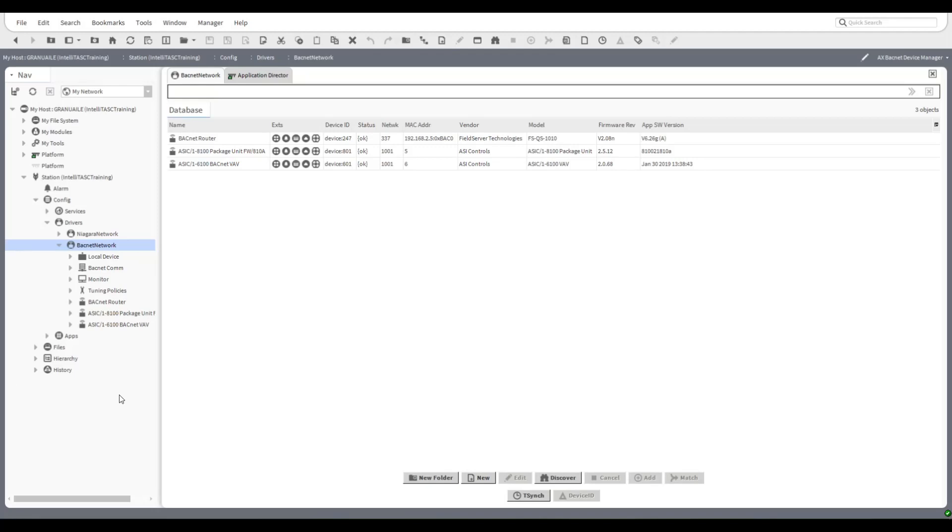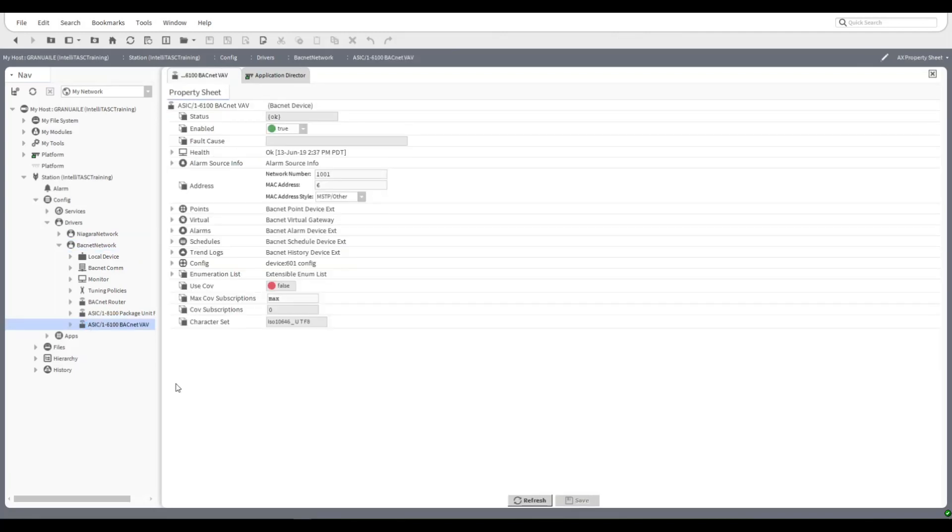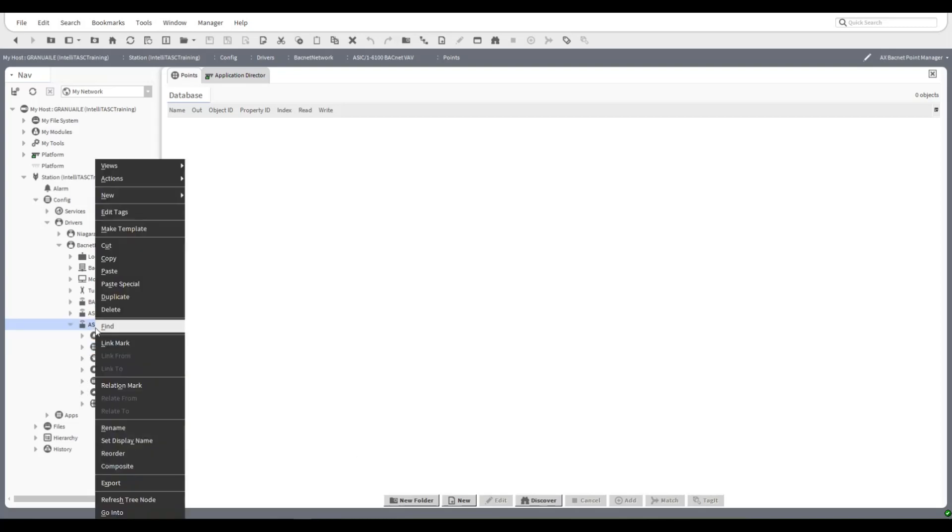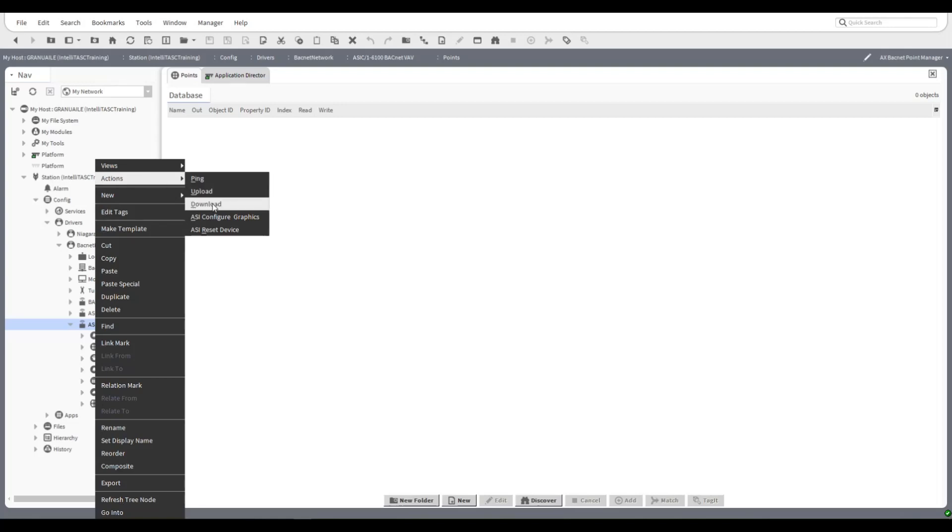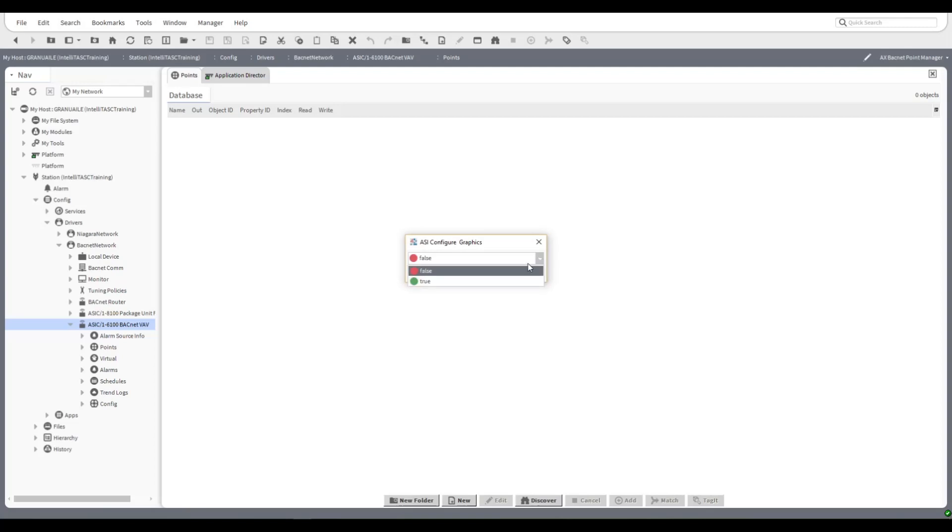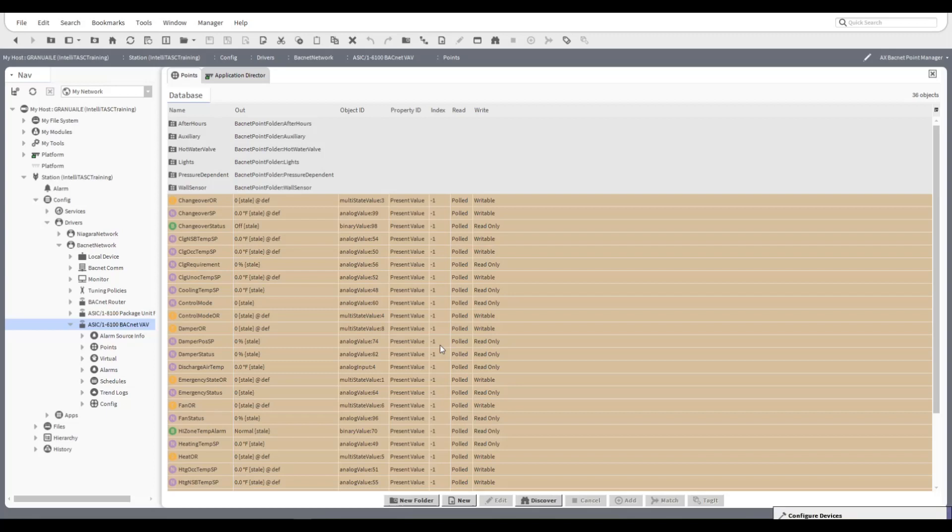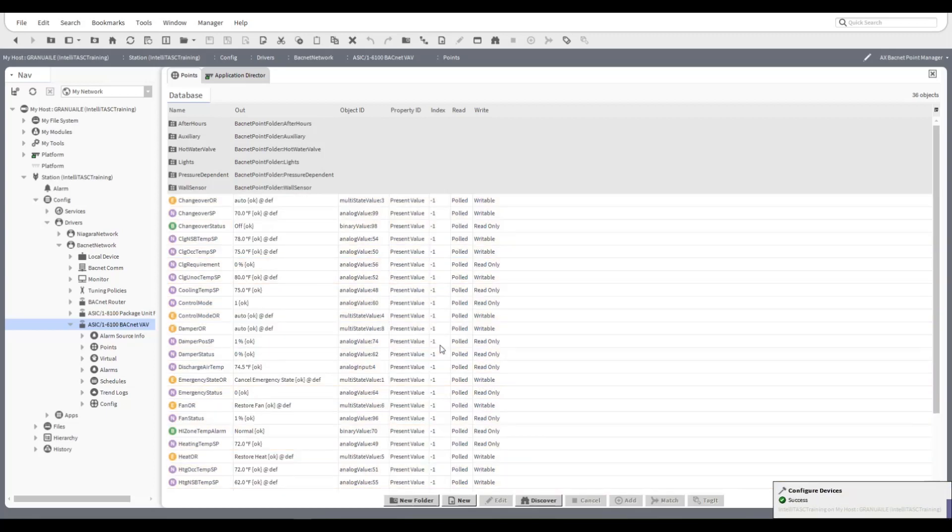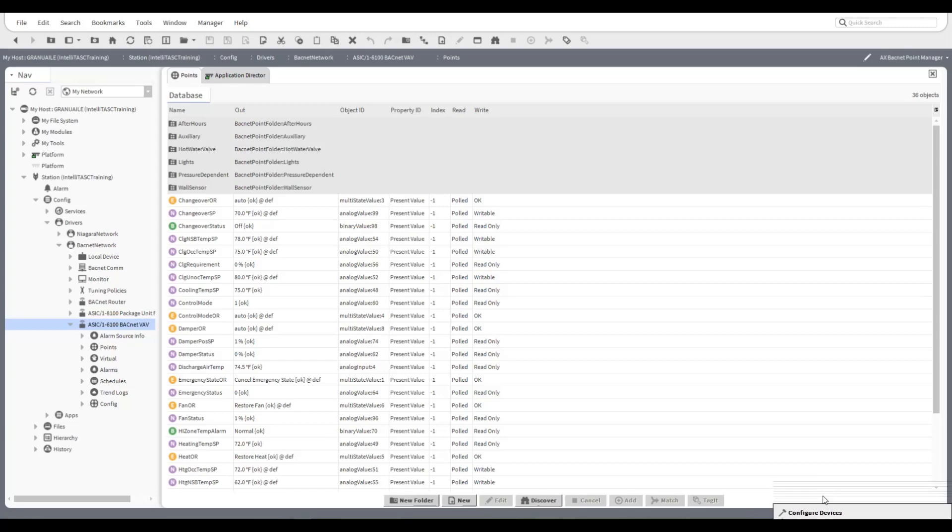For the purpose of this exercise what we will do is configure the 6100 device that I have here. If we take a look currently and double click on the device we just get the property sheet as usual. The points list is empty because all we did was discover the device and bring it in, we didn't bring in the points. Now at this stage you could hit discover and discover the points and bring them in, we're not going to do it that way. We're going to right click, choose our actions, and say ASI configure graphics. It's going to ask you to confirm, we hit true and away we go. Straight away you see the points get configured and on the right hand side you see here configure device success.